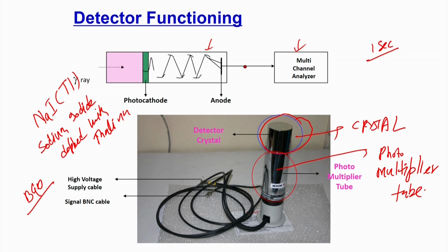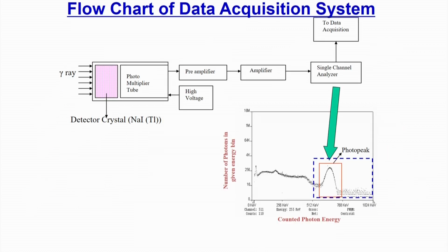Okay. Now, the second hardware which is important, which I have been mentioning till now, is a counter which is placed after the detectors. There have been several advancements in the RPT hardware. Earlier this system used to be very huge, but with the development of modern electronics, the system size has now been reduced. So, what we need actually, these detectors, as I said, have photodiodes, and those also need energy.